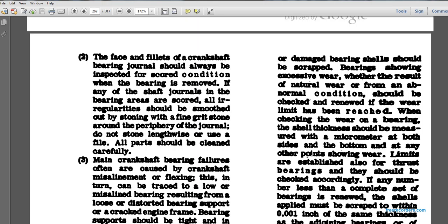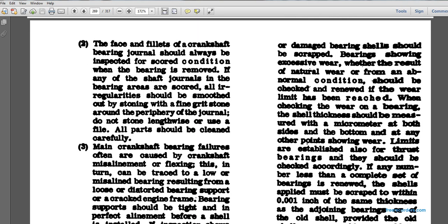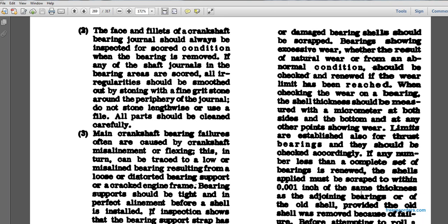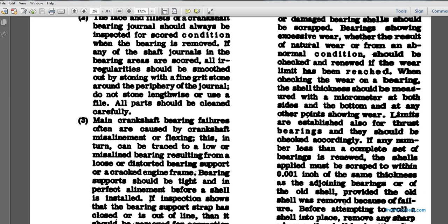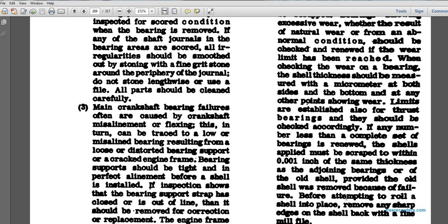Bearings showing excessive wear, whether the result of natural wear or an abnormal condition, should be checked and renewed. In checking the wear on the bearings, the shell thickness should be measured with a micrometer at both sides, at the bottom, and at other points showing wear. Limits are established also for thrust bearings, and they should be checked accordingly. If any number less than a complete set of bearings is renewed, the shells applied must be scraped to within 1/1000 of an inch of the same thickness as the adjoining bearings and of the old shell, provided that the old shell was removed because of failure.